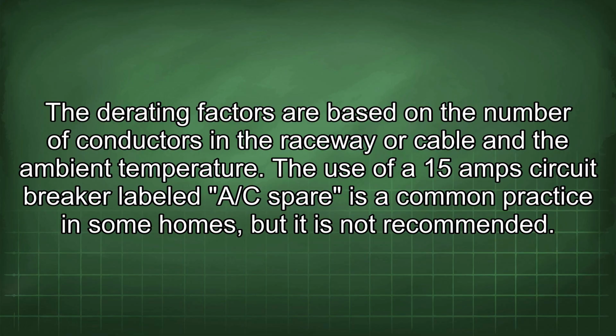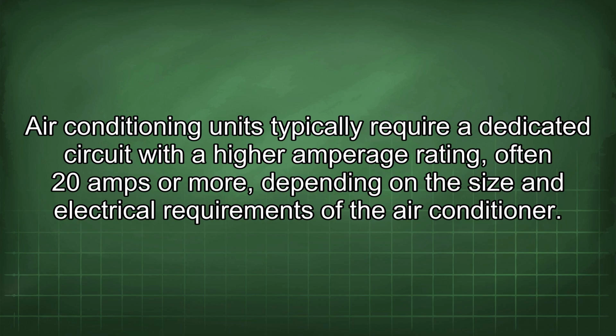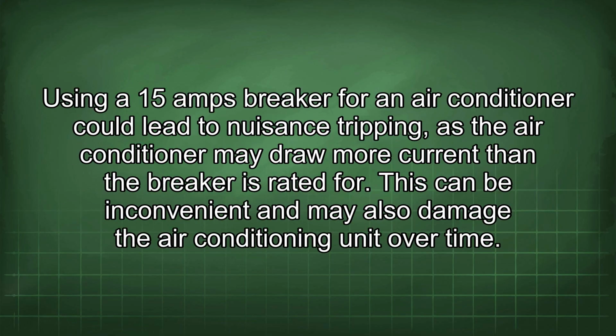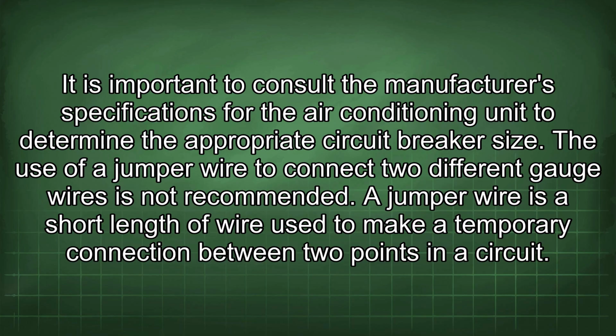The use of a 15-amp circuit breaker labeled as A/C spare is a common practice in some homes, but it is not recommended. Air conditioning units typically require a dedicated circuit with a higher amperage rating, often 20 amps or more, depending on the size and electrical requirements of the air conditioner. Using a 15 amp breaker for an air conditioner could lead to nuisance tripping, as the air conditioner may draw more current than the breaker is rated for. This can be inconvenient and may also damage the air conditioning unit over time. It is important to consult the manufacturer's specifications for the air conditioning unit to determine the appropriate circuit breaker size.